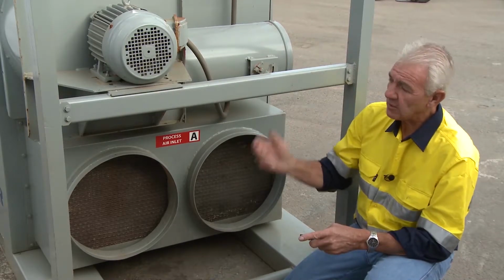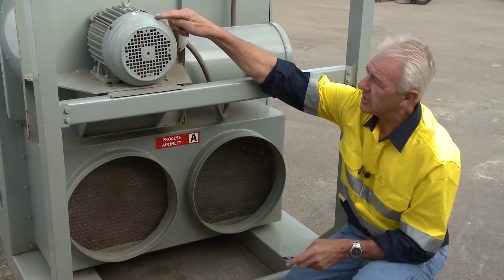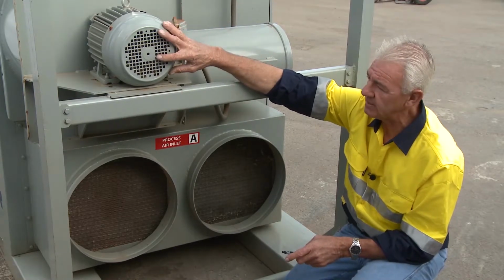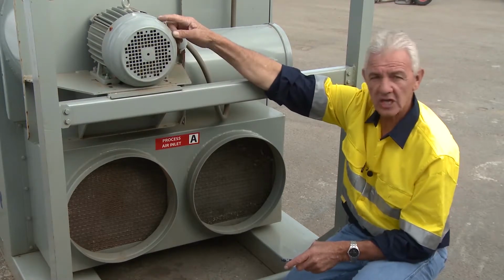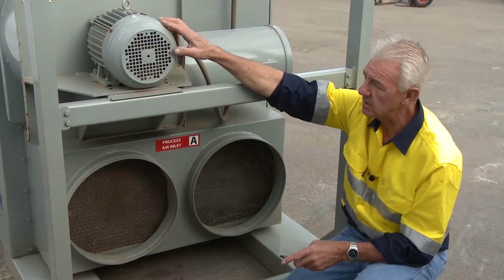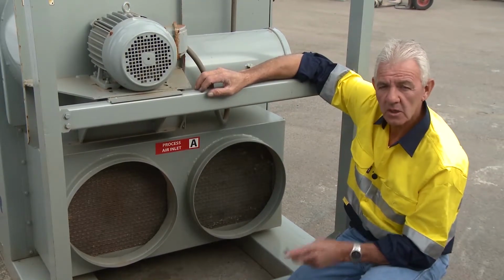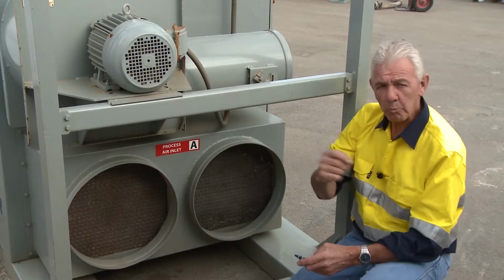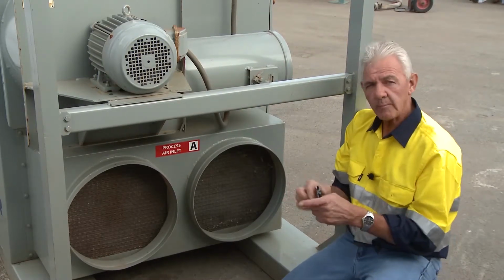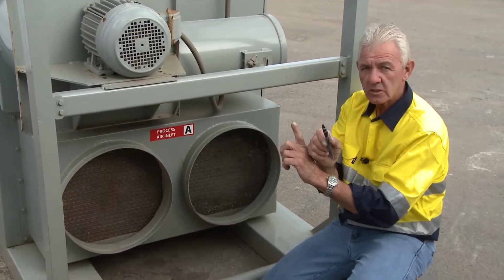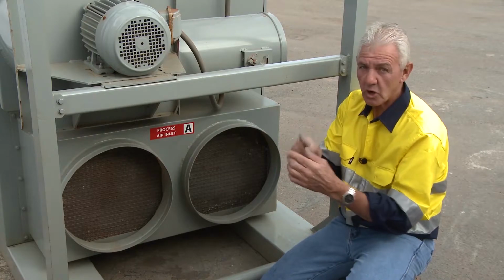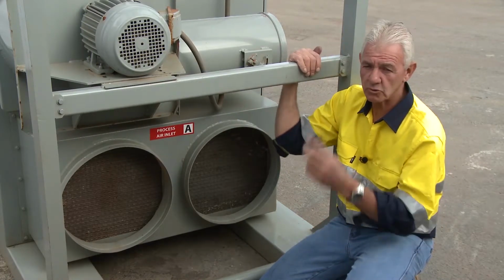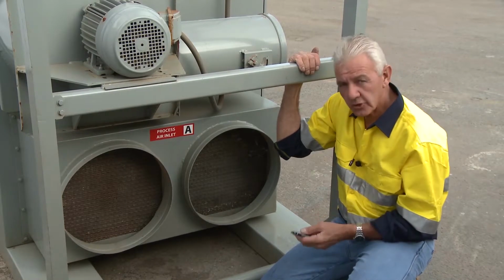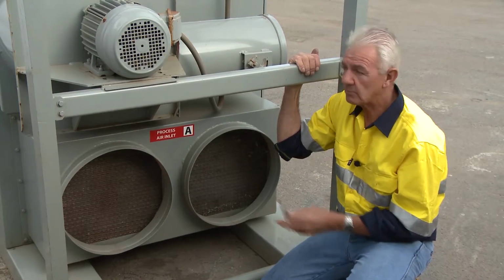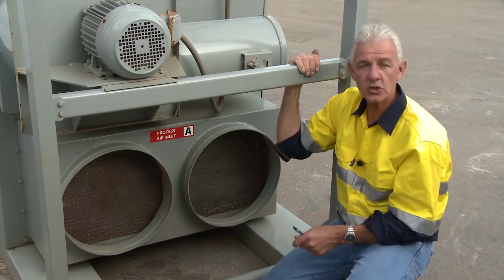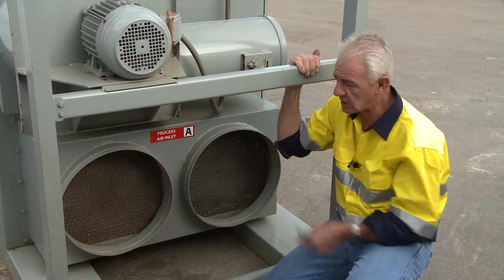So what that consists of is if you plug this into power and you find that there's an arrow on the top of these outer housings to protect the fan, if you find that the fan's not spinning in conjunction with the arrow rotational spin, you think, hang on a minute, that's going backwards. All you need to do is contact an electrician or BlastOne and they'll send an electrician. What that means is all they have to do is reverse the 3-phase. So there's just 2 wires to reverse to bring this back in the correct rotational spin. So that's something I do check the minute I install this machine to make sure that the rotation for all these motors is correct. If it's not correct, of course the machine won't run properly.